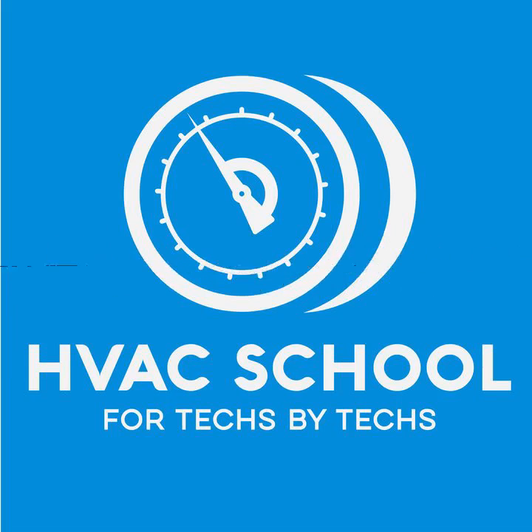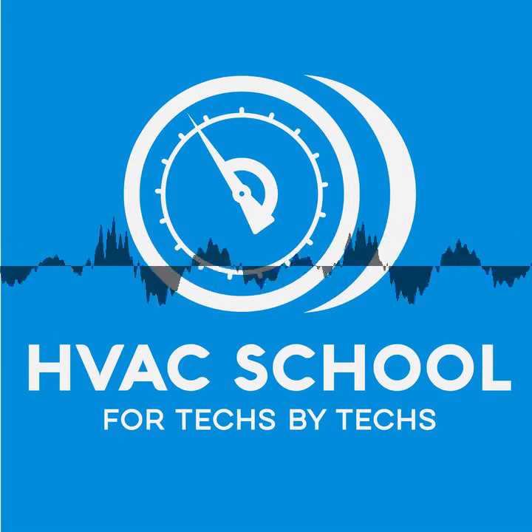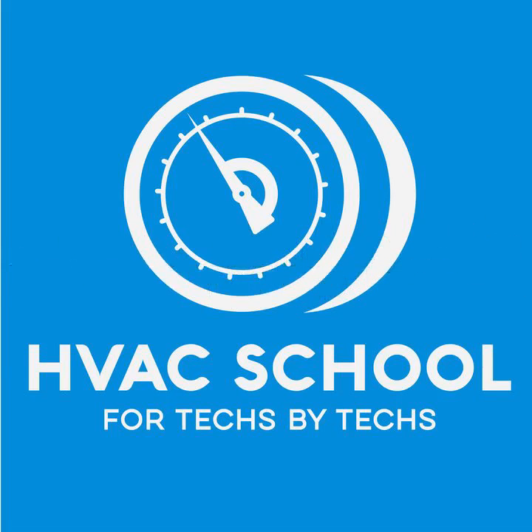My question would be, how much superheat do you have? If you've got a 30 or 28 degree evaporator temp and you've got 8 degrees of superheat, it ain't a TXV problem. It's an airflow or load problem. Now, if you've got a 28 degree evaporator and you've got 30 degrees of superheat, now it's a refrigerant flow problem. Okay, it's not a load side problem. So those two different results right there require a different approach to the problem.